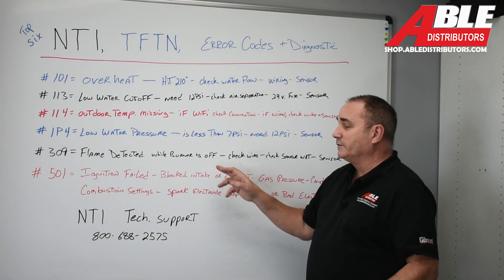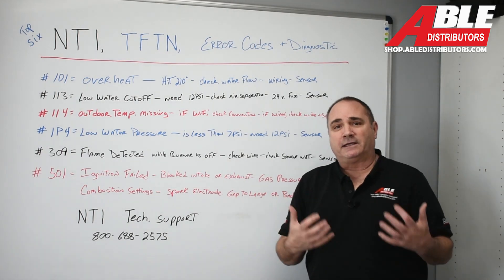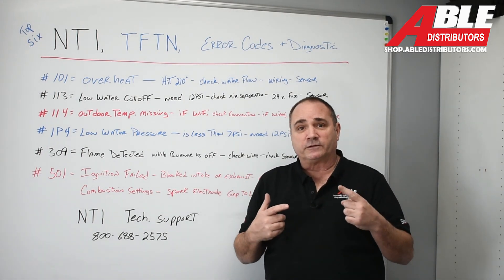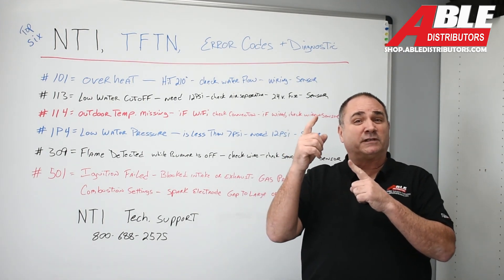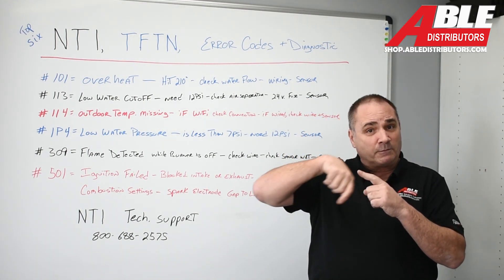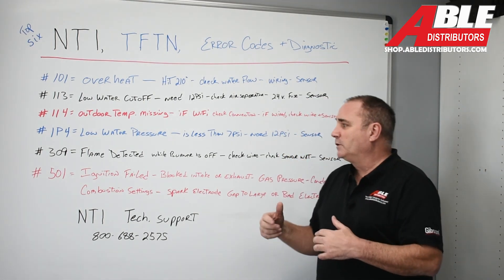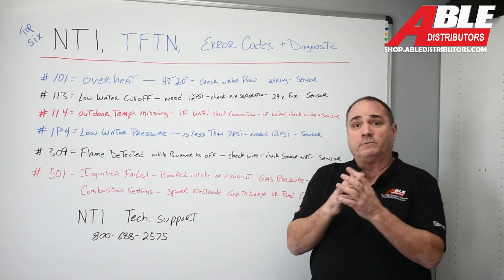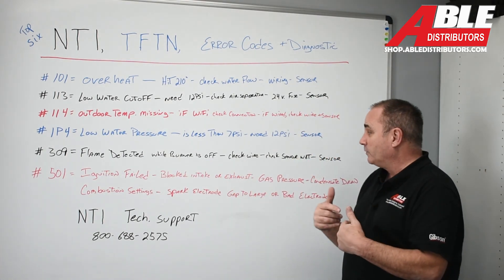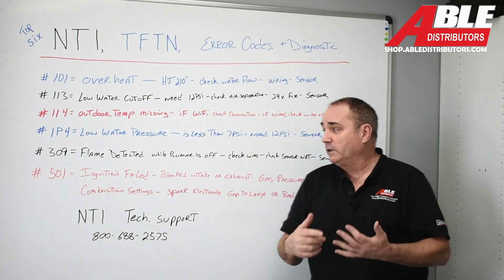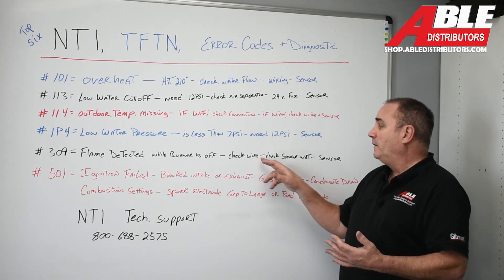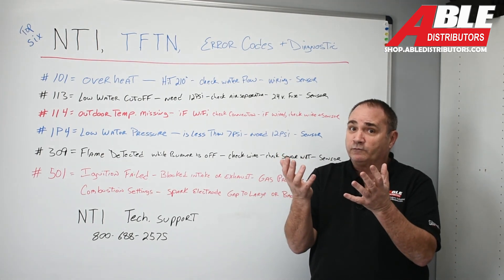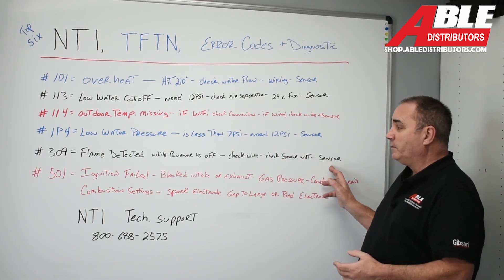Flame detected while burner is off. I always like this one because flame detection in most things, including a furnace, is just a trickle of electricity that feeds back through ground. So if you're detecting flame while the burner is off, it could be wires that are pinched, shorted, or broken. It could be that the sensor is wet, or the heat exchanger is filled with water, or it could be the sensor itself.